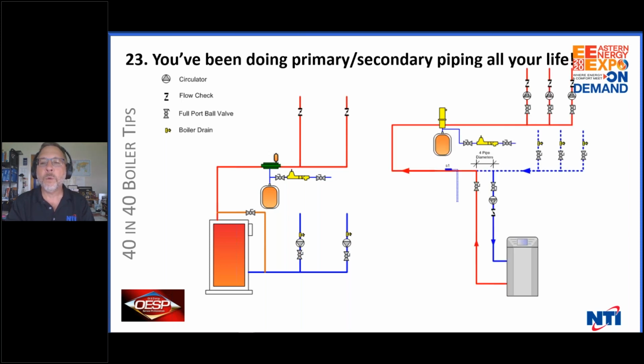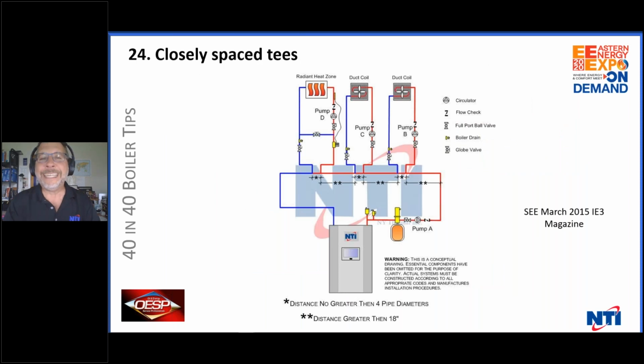But today, we want our boilers to condense. So now we do primary, secondary by 2 closely spaced T's. The 2 T's are so close, 4 pipe diameters, that there's no pressure difference between them. So no water will go through there if the circulator on the boiler's not running. So it gives you true isolation where the boiler can have its flow to keep it clean and so it doesn't percolate, and the system can have its own flow. The system can be at a 20-degree delta T while the boiler's at a 35-degree delta T, so the boiler can stay in condensing mode longer. The system can come up to temperature slower, use outdoor reset, and the boiler can modulate. Closely spaced T's are phenomenal.